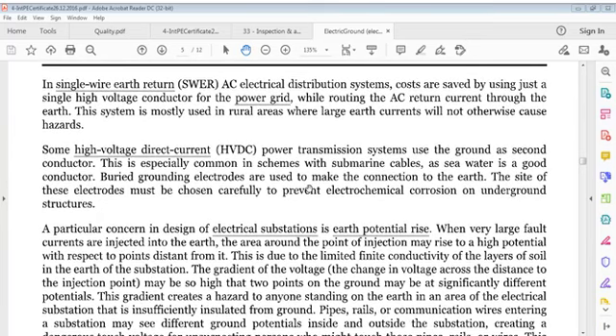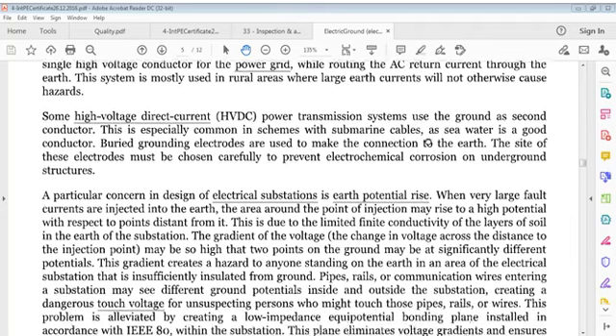Some high voltage direct current, HVDC, power transmission systems use ground as a second conductor. This is especially common in schemes with submarine cables. As seawater is a good conductor, buried grounding electrodes are used to make connection to earth. The site of these electrodes must be chosen carefully to prevent electrochemical corrosion on underground structures.